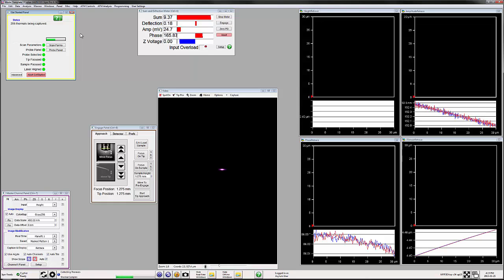This is important, because when you press a cantilever against a surface, as you would with traditional calibration methods, you run the risk of dulling or fouling your tip. By the end of these pre-engage steps, GetStarted will have calculated my ideal gain, scan rate, amplitude, and set point based on my earlier inputs and on these measurements. From here on out, I won't be touching the computer. I'll just stand back and watch the show.